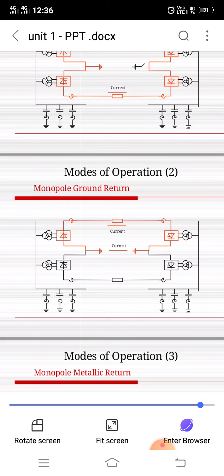Due to this physical reason, the direction of current does not change — meaning the thyristor valve conducts current only in one direction. When the direction of energy flow is reversed, the polarity changes to the supply side and the rectifier becomes an inverter, delivering energy to the AC network. The average value of the direct voltage as a function of the firing delay defines the mode of operation.